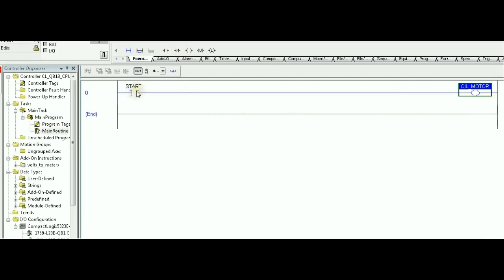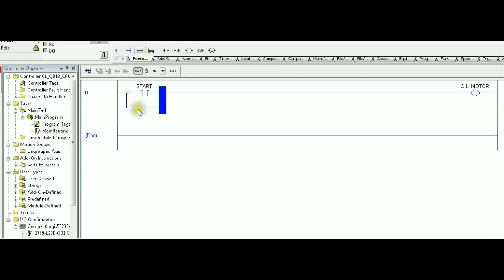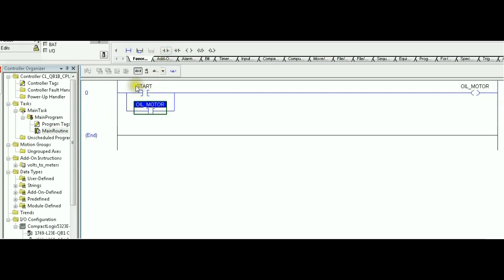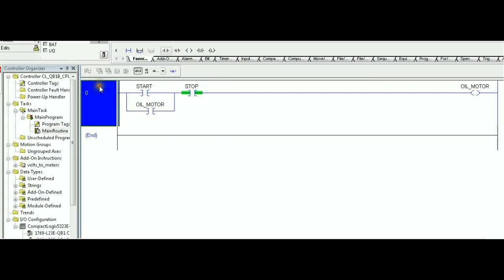And remember, the start is a momentary switch, so we are going to require latching requirement, which is another XIC instruction referring to oil motor that's going to bypass the start once the start is released. That's my on section of this rung. We also need the off condition, which is the stop. That's an XIC referring to stop. I'm moving a little bit fast with these instructions because we have done them before. We have done this example.